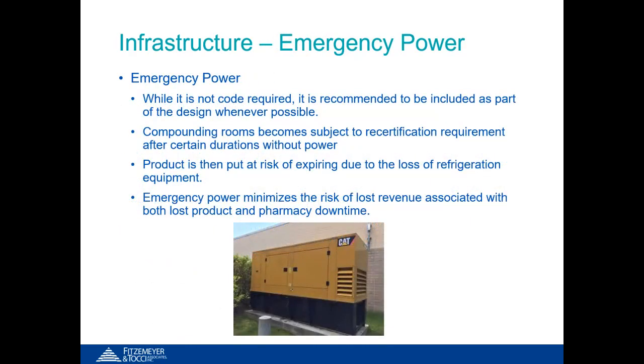While it is not code required, we highly recommend that emergency power be included as part of the design whenever possible. Compounding rooms become subject to recertification whenever the airflow or air change requirement or the temperature and humidity requirements fall outside of the desired levels, and this can easily occur if there's loss of power for a short duration. Additionally, product is put at risk of expiring due to loss of refrigeration equipment. Emergency power can greatly minimize the risk of lost revenue associated with both lost production and pharmacy downtime.